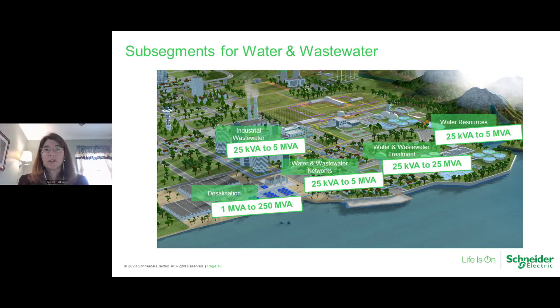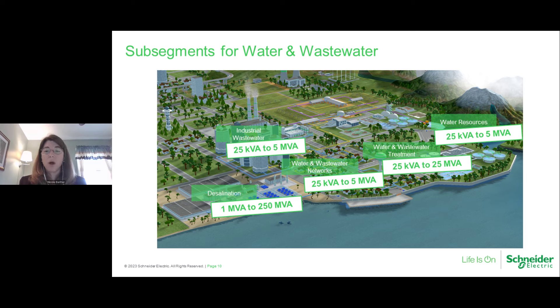Networks consist of pumping stations ranging from small water-lifting and local distribution to very large stations for long-distance water transmission. Industrial wastewater facilities treat wastewater produced after manufacturing processes — heavy water users include food and beverage, paper, chemicals, petroleum refineries, and metals. Semiconductors are a fast-growing industry where water is critical in chip production — specifically ultra-pure water, or UPW, which is thousands of times purer than drinking water. It takes roughly 1,400 to 1,600 gallons of municipal water to make only 1,000 gallons of UPW, with semiconductor facilities using upwards of 5 million gallons per day.